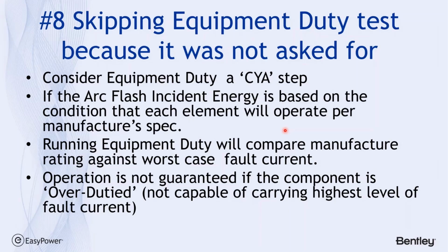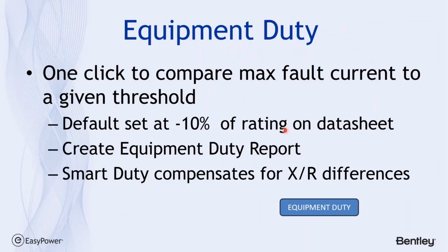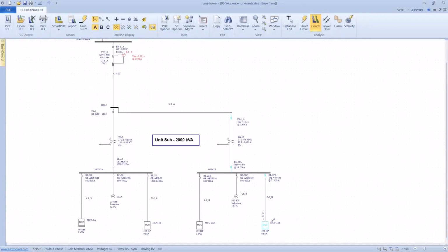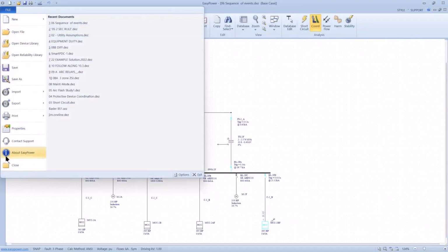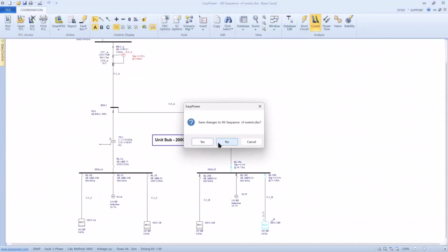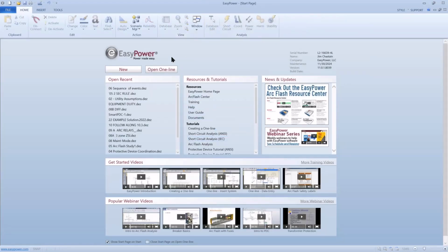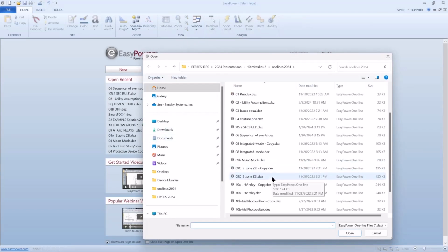And as we showed, running the equipment duty will compare the manufacturer's rating against the worst case fault current. The operation of the breaker is not guaranteed if the component is over-dutied. Now, it's relatively simple to verify. I've seen situations where people, granted this is a new user mistake, didn't realize that equipment duty was that easy to do, and they just didn't know to click the button. So here's what it looks like. I don't mean to harp on this, but it just doesn't make sense to do a study without one simple button click to verify equipment duty is adequate.